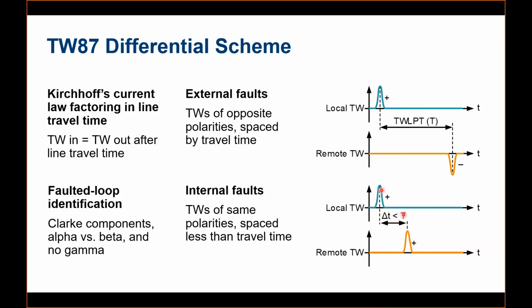So this is again linking the concept with the application. Positive peaks with the same polarities and a time less than the characteristic, fixed or constant time is a clear indication that it's an internal fault. In this principle, your TW87 will decide whether the fault is internal or external. The only thing that is creating some delay in this process is the communication between the relays. For this particular application, we need a direct fiber between both the relays so that they can communicate in a very fast manner and exchange the information, because the local relay will need its own information as well as the remote relay information to decide whether it's an internal fault or an external fault. So TW87 will need a direct fiber communication between both the relays.